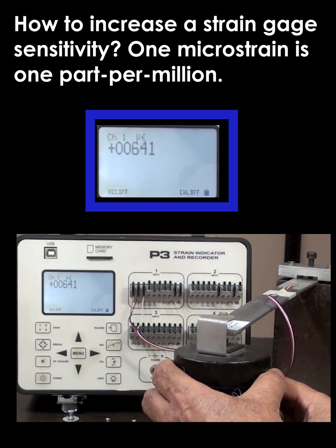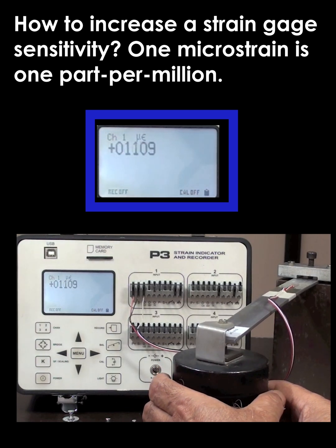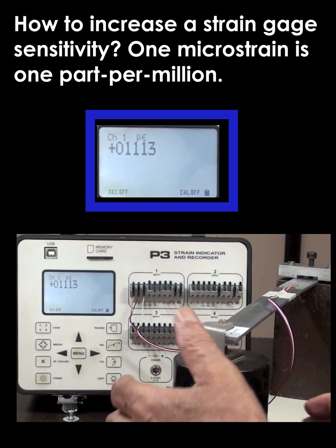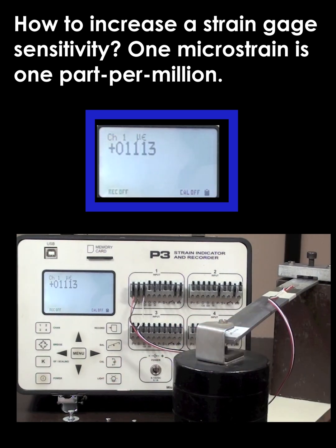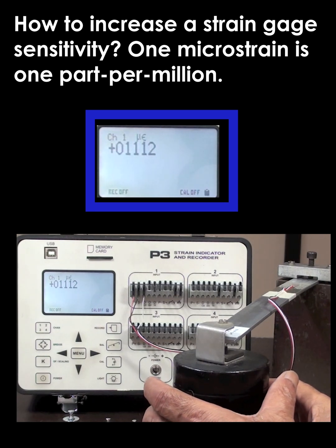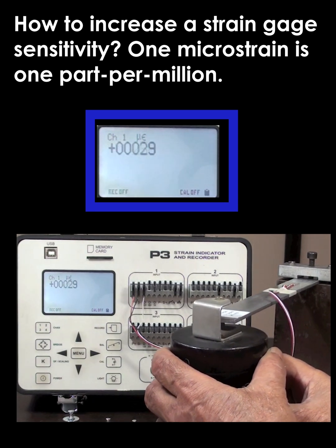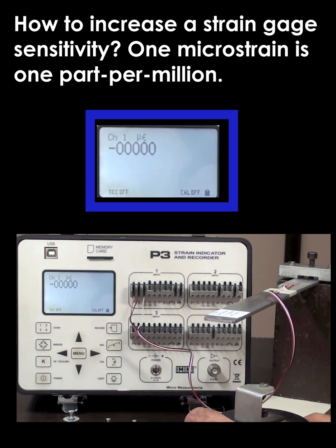Now you can see we're at a good zero condition. We take our two kilogram weight, put it on the end of it, and we're expecting 1113 microstrain. Once we let go of the weight, we get exactly that. This shows an example of the capability of an electrical resistance strain gauge.